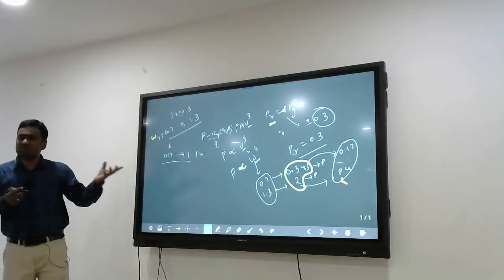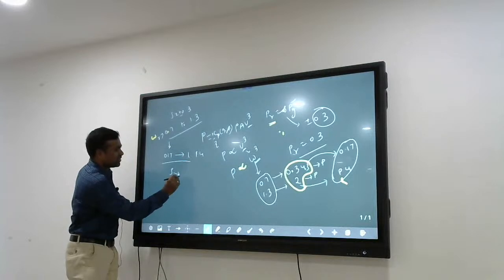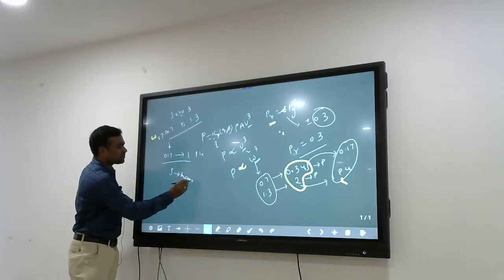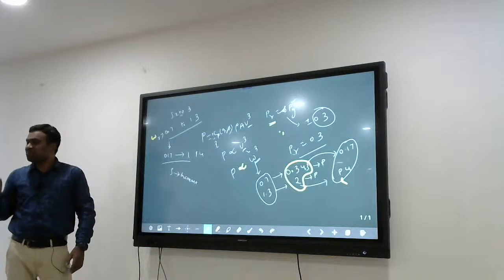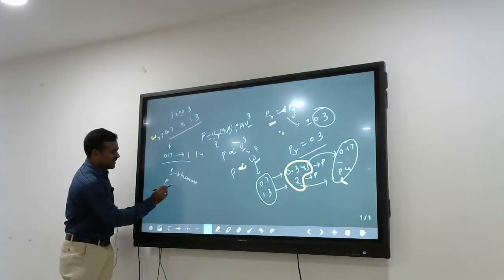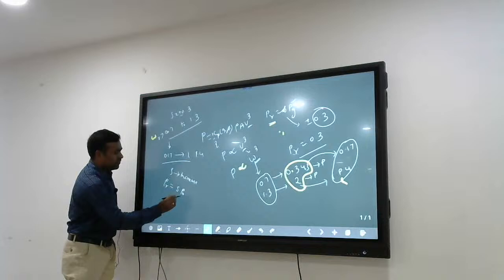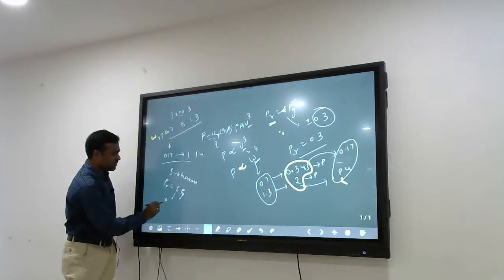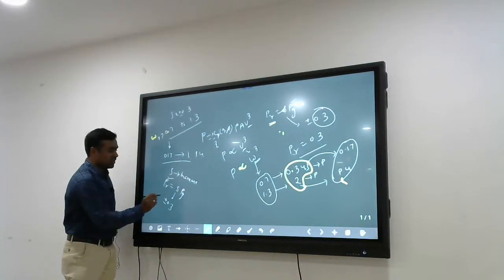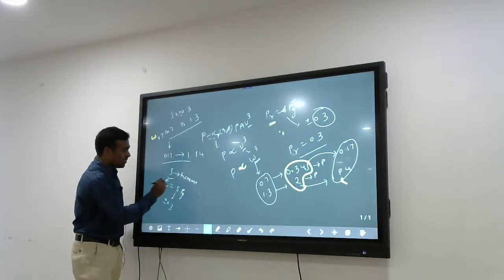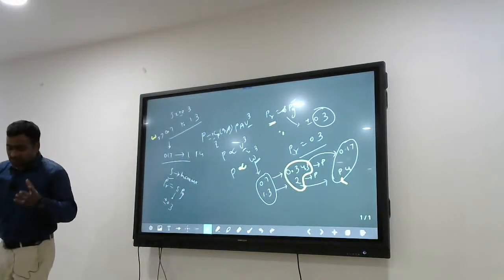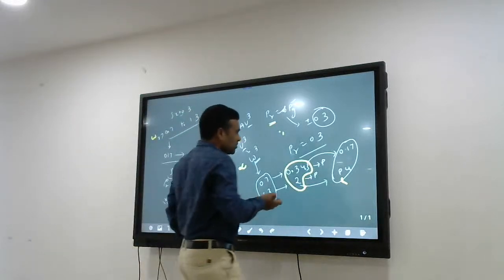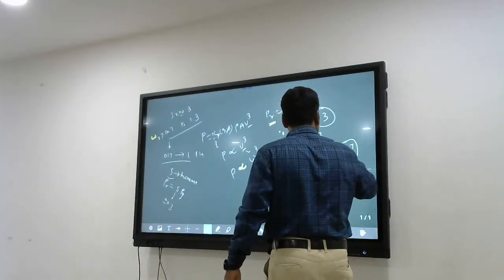Another problem is, if I increase my slip, then my converter rating will increase, because PR is S times PG. If I restrict my S to plus or minus 0.3, my converter rating is 0.3 only. Suppose I make it 0.4, then I have to increase my converter rating. So I won't get much advantage even by increasing the converter rating, just going below this power range. So normally people fix the power rating as this one.